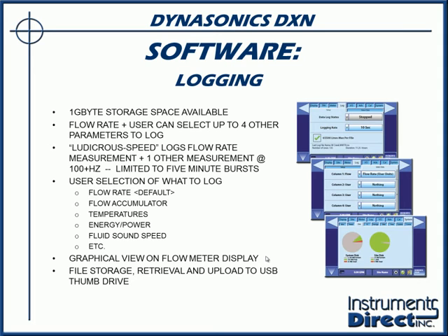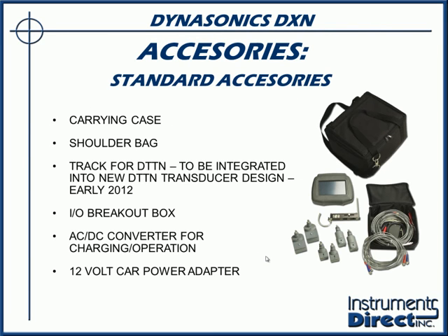You can program up to 4 separate parameters of data that you'd like to log, and it can go ultra fast, to any time sample you basically want. So you can program the sample rate there. And as far as data that you can select, you could record the flow rate, the totalization, temperatures if you have the RTD package, energy, power, sound speeds, and the list goes on. What you see on the screen, you have the ability to check those individual items. Then you'd store your data on a thumb drive.